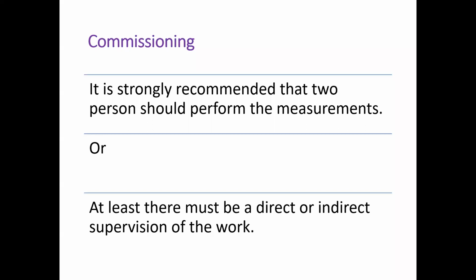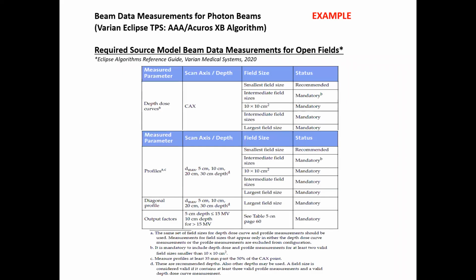It is strongly recommended that two persons perform the measurements. It does not mean that someone very experienced cannot perform the commissioning independently. Yes, they can, but there should be a second pair of eyes to verify things, just to cross-check. For example, if I have received a value of 67.5% and I have mistakenly written 77.5%, that will make a hell of a difference. Or at least there must be direct or indirect supervision of the work, because we know that in many places more than one person is not available. So at least there should be direct or indirect supervision.